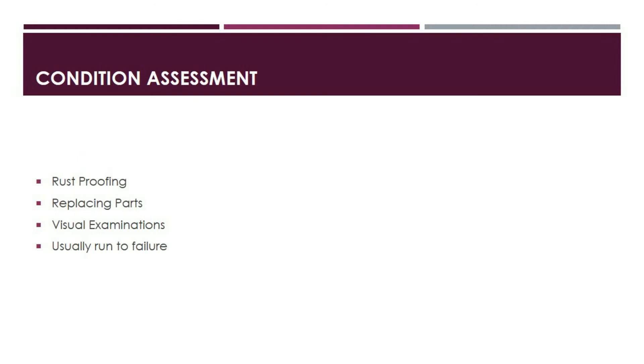Visual examinations provide a wealth of information about transformers' condition. Visual checks can reveal the presence of oil leaks, fractured bushings, and corroded tanks. In the case of pad mount and vault transformers, the condition of the pad and vault also influences the transformer replacement criteria. Utilities may replace the appropriate transformer together with the pad or vault if the pad or vault is broken or degraded beyond repair.